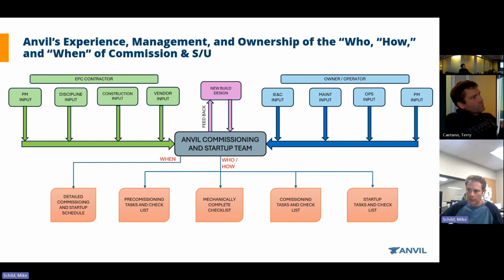Typically that's followed with a sign off. A lot of the milestones that the contractor is going to be getting payment for have to do with their mechanically complete date. I've had jobs where if this mechanically complete date is done so many weeks in advance of what was originally scheduled, the contractor would get bonuses for it, and vice versa. If they're late, they may be paying penalties for that. Very important to have that defined, and defined early on. Commissioning tasks and the startup tasks, we'll look at what's involved with that as well. And again, a lot of people forget about the startup task. It's no different than doing a construction schedule. There's a certain sequence of startups that you have to perform in order to get this done.